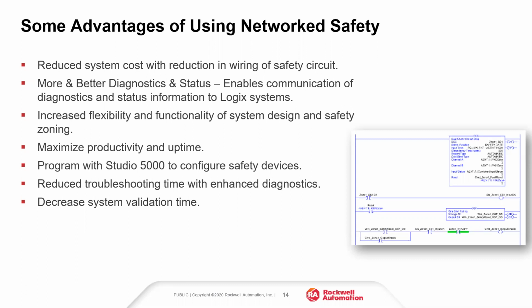Increased flexibility is another advantage of CIP Safety. If you don't like the safety strategy, if it's not fitting your operation, then you can simply reprogram that strategy. You don't have to rewire that strategy. Now, on smaller pieces of equipment, you may want to continue with wired safety, but in larger pieces of equipment, you might consider going to safety over Ethernet IP. The idea is to maximize productivity and uptime, and make the equipment not only safe, but also productive.